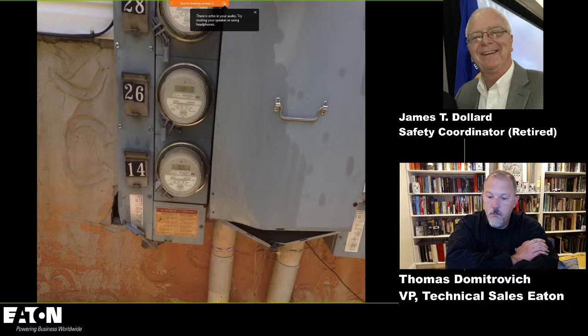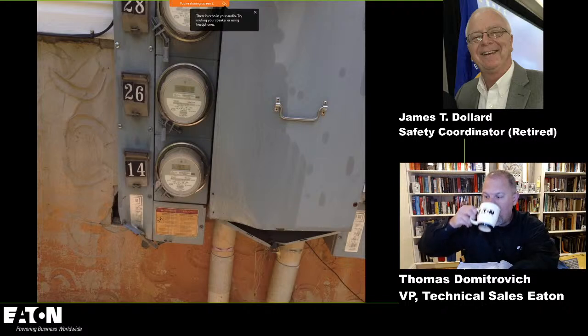The push to change that and say that you needed to maintain all of your emergency equipment actually came from a representative on the committee that represented the Healthcare Association. The reason they wanted that language in: we all knew that if you've got a new installation, 700.3C doesn't hold you to anything. But your state-run health commissions are now aware of that. They know that if you adopt the 2020 NEC, and I think that went in in 17, yep, you are required to maintain all of your emergency equipment, and they can force the hand of the healthcare facilities to do that, because they're notorious for not maintaining their equipment. It's a healthcare facility, but they don't maintain their generators, they don't maintain their transfer switches, they don't maintain low voltage power circuit breakers, and it's a problem.